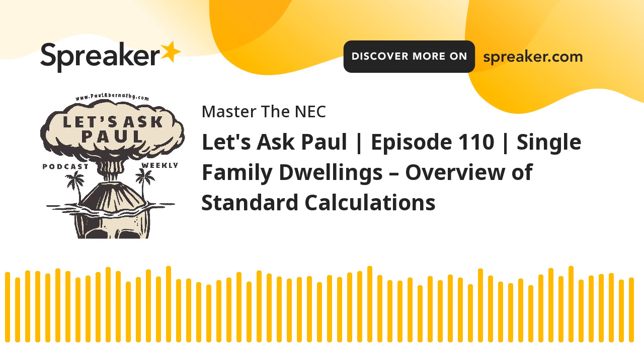Remember now, this table is only applicable if there is no adjustment or corrections to take place. If there's an ambient temperature other than 30 degrees Celsius, 86 degrees Fahrenheit, or by some weird chance, a rarity, you have more than 3 current carrying conductors, then this table is useless. You have to do the same kind of calculation using 310.16 that we always do, applying adjustment and corrections and so on. And then you still can use the 83%. The conductor can't be smaller than 83% of whatever the service or feeder rating is. So you still can meet the 83%. It's just you're not going to be able to use this table to shortcut.